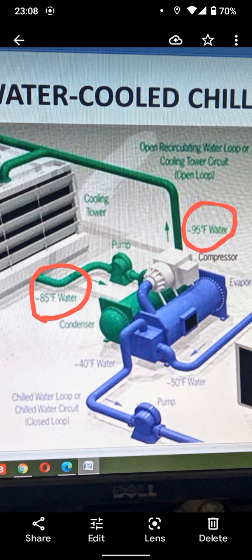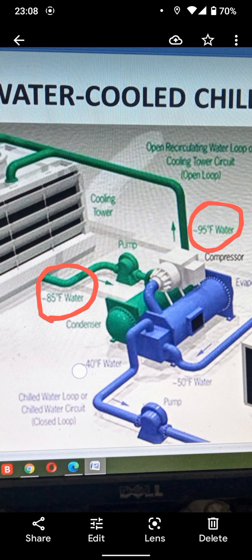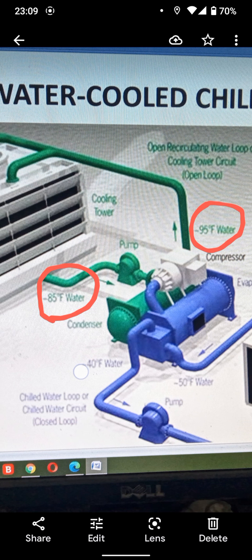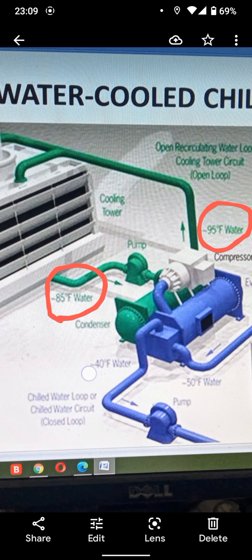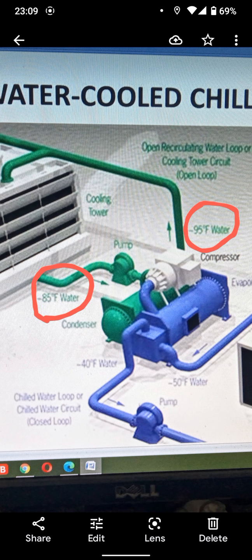You cannot find in a book what to do when the supply condenser water temperature reaches 94 degrees. What does the book tell? The technique was to remove the other regulating valve, start two more pumps, start two more condensers, and restrict the electrical demand to 55-60%. No, the manual does not guide you this way. The manual is straightforward. This selection sheet says you should provide this centrifugal chiller 85 Fahrenheit temperature, otherwise it's surging. But the ground reality is totally different. You are under pressure from your manager and everyone pushing you to do anything. So we did this, and thank God, the chiller is running successfully.